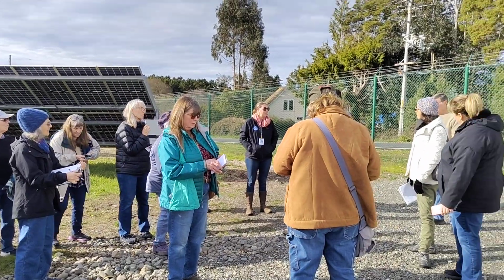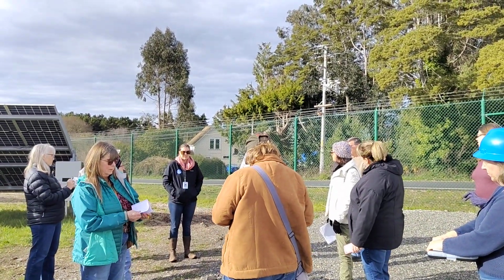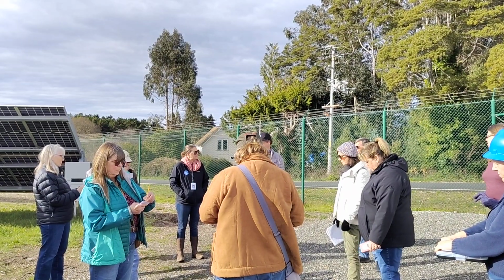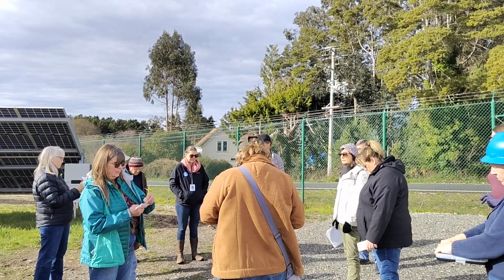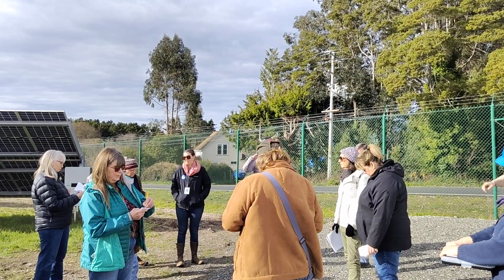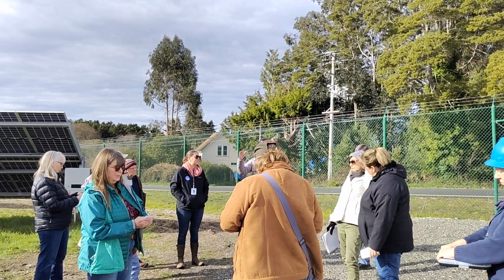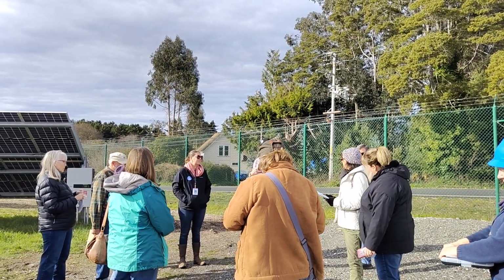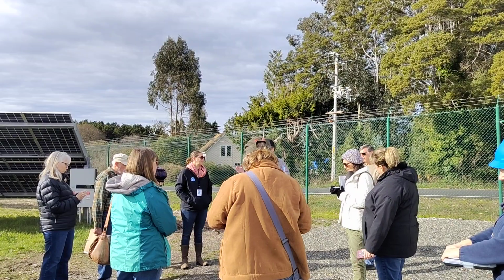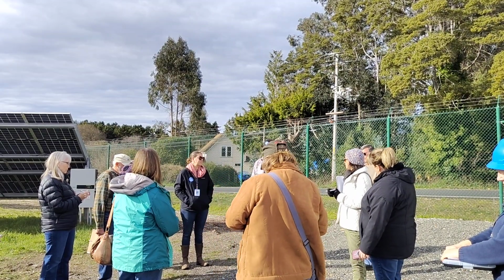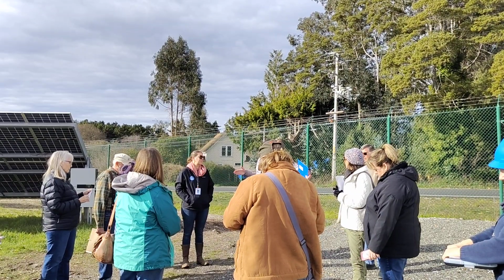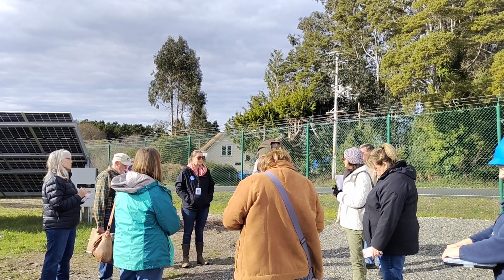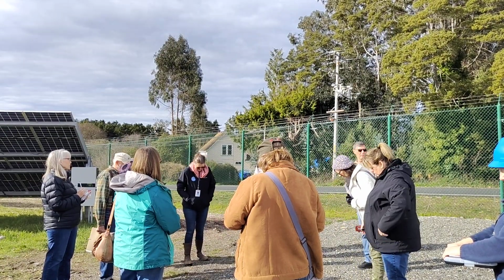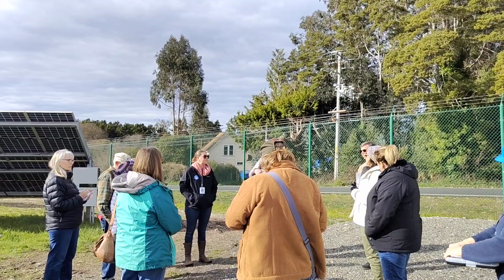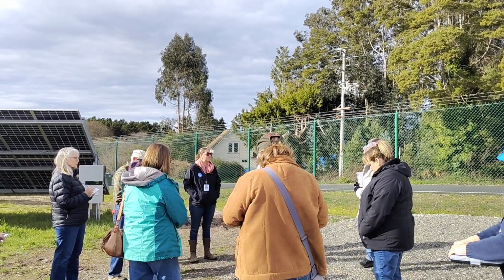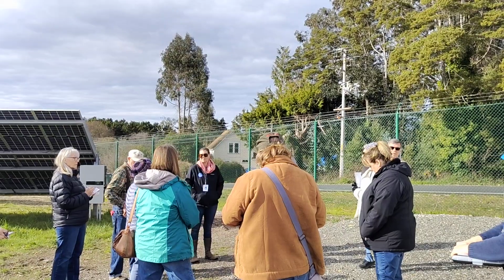From a design perspective, you pretty much want to lay out your criteria and say, okay, I want 20 megawatts, and then your various respondents will tell you the footprint size. If you have sound as a requirement, you specify what kind, and have the manufacturers do the sound engineering for you, stating the decibel level that would be hit by a system of that size, the footprint needed, and the setback required for your fencing from a safety perspective. Put the work on the respondents to tell you, for their technology and design implementation, what size you're going to need.